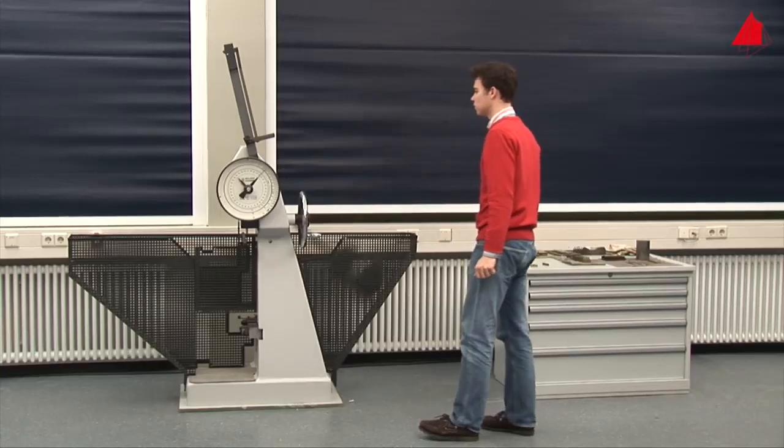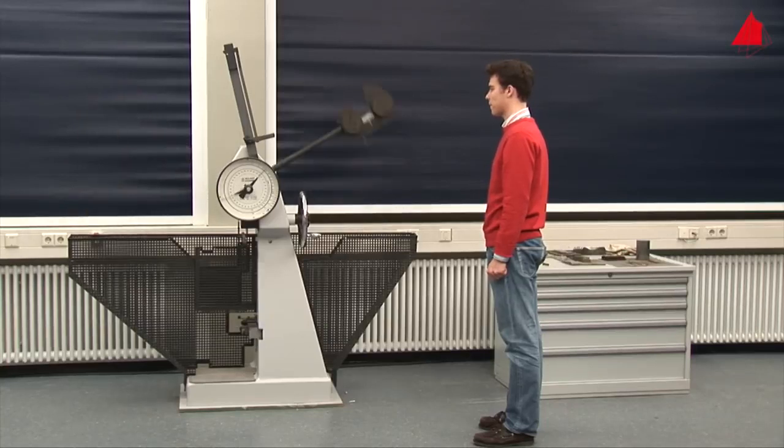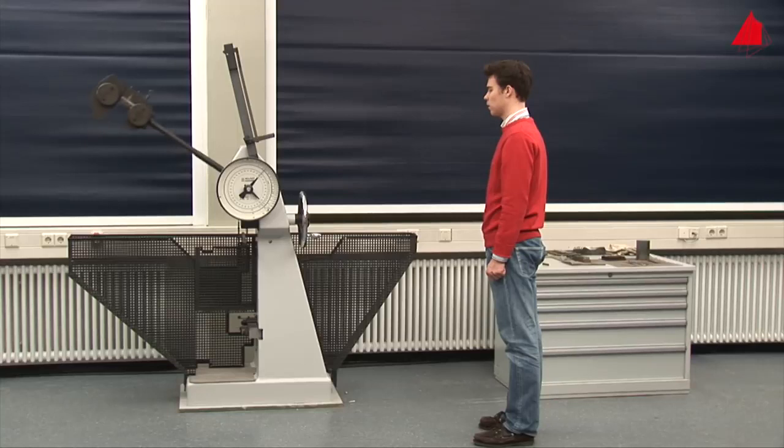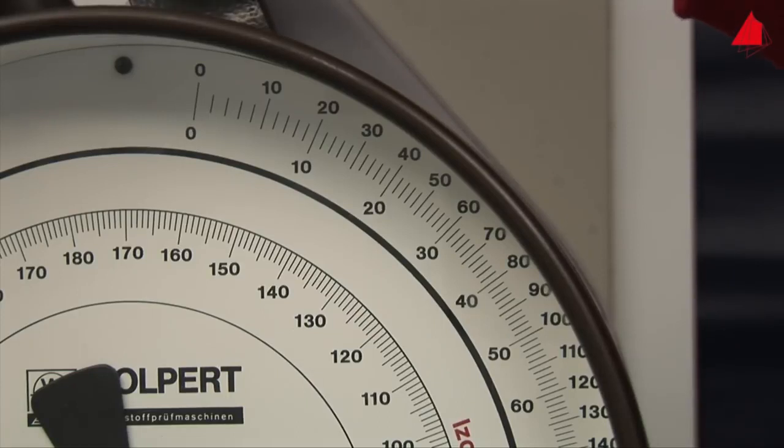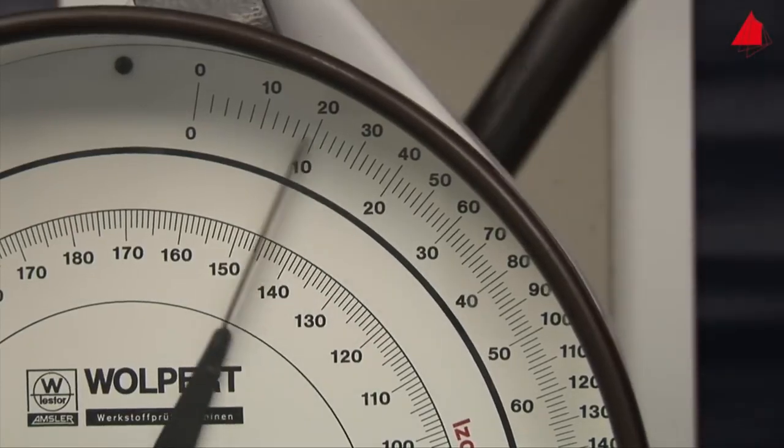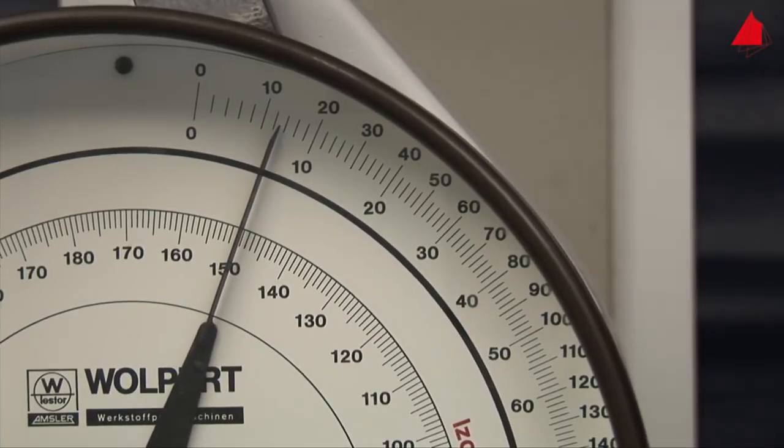The pendulum is released. It swings downwards and hits the specimen with its rounded hammer pin. The specimen absorbs part of the pendulum's energy so the pendulum doesn't reach the full height on the other side. The amount of energy that has been absorbed by the specimen can now be read off at the position of the drag indicator. It only amounts to 13 joules in this test.